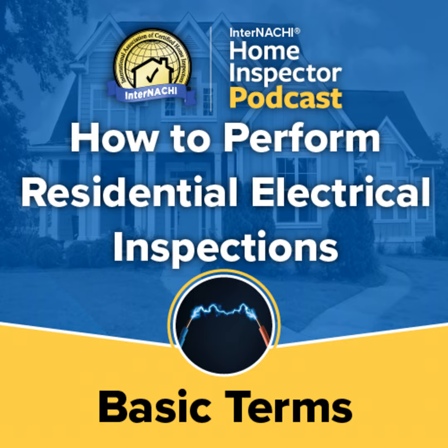SE and SEU cable. Service entrance, or SE cables, are used for services. SER and SEU are 2 common types of SE cables. Type SE, style SEU service entrance cable is primarily used to convey power from the service drop to the meter base and from the meter base to the distribution panel board when the main disconnect is installed at the main panel board. SEU is an unarmored service entrance 3-wire cable with 2 conductors and a neutral.